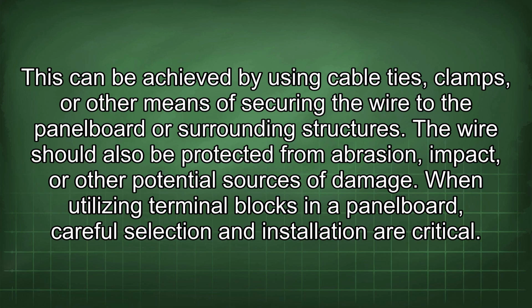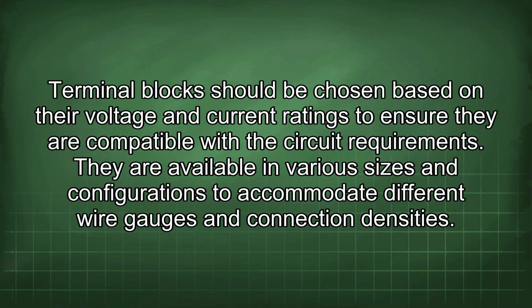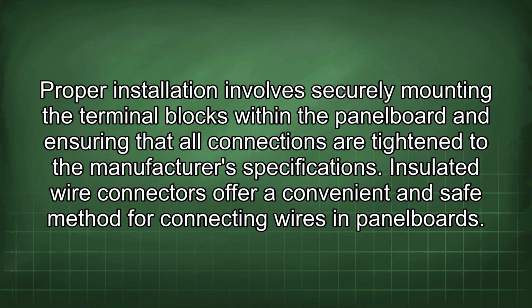When utilizing terminal blocks in a panel board, careful selection and installation are critical. Terminal blocks should be chosen based on their voltage and current ratings to ensure they are compatible with the circuit requirements. They are available in various sizes and configurations to accommodate different wire gauges and connection densities. Proper installation involves securely mounting the terminal blocks within the panel board and ensuring that all connections are tightened to the manufacturer's specifications. Insulated wire connectors offer a convenient and safe method for connecting wires in panel boards.